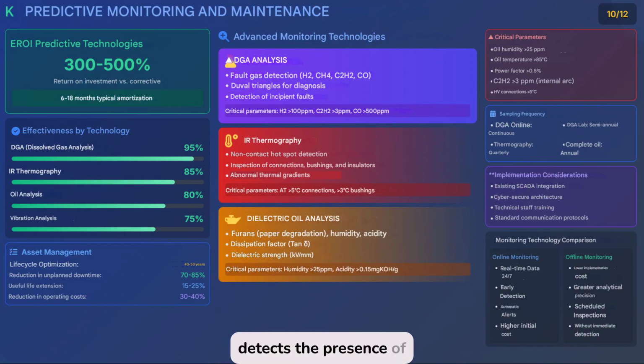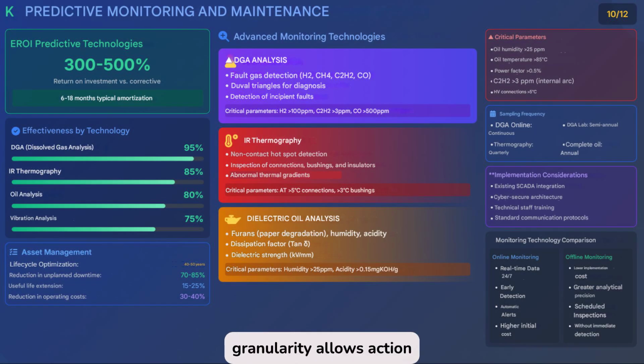This analysis detects the presence of gases, such as hydrogen, methane, ethylene, or carbon monoxide, which are early signs of internal failures in transformers. If we add to this the interpretation using Duval's triangles, we obtain a proactive diagnosis based on parameters such as H2 above 100 ppm, C2H2 above 3 ppm, or CO above 500 ppm. This level of diagnostic granularity allows action to be taken before the failure escalates and affects the entire system, avoiding not only repair costs but also contractual penalties, supply interruptions, and safety risks for technical personnel.